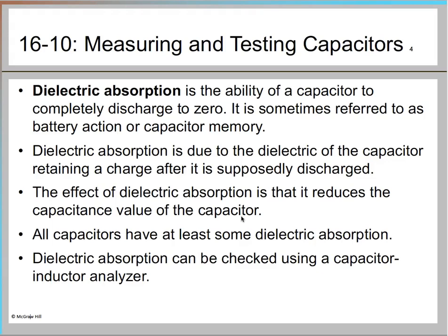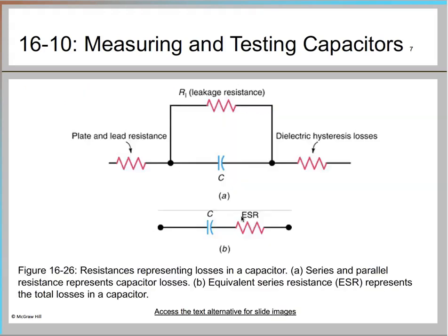Dielectric absorption can be checked using a capacitor inductor analyzer. All capacitors have some amount of dielectric absorption, and you can see that on the data sheet as well. You can use the capacitor inductor analyzer, which we also have in our lab, to test the dielectric absorption.